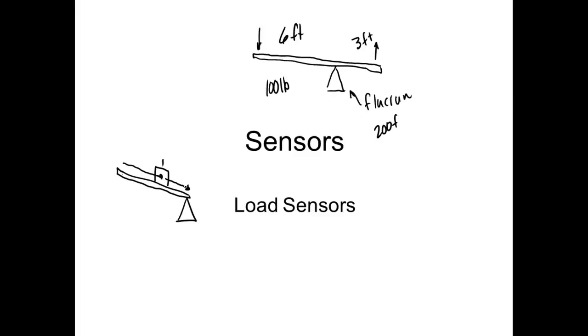You know, I could use pressure. So if I've got a big tank that's full of a liquid and I know its specific gravity, then I can literally come down here at the very bottom and put a pressure sensor, because the pressure now would be proportional to the weight. Right? Does that make sense? So we got pressure sensors, which we'll look at later on.